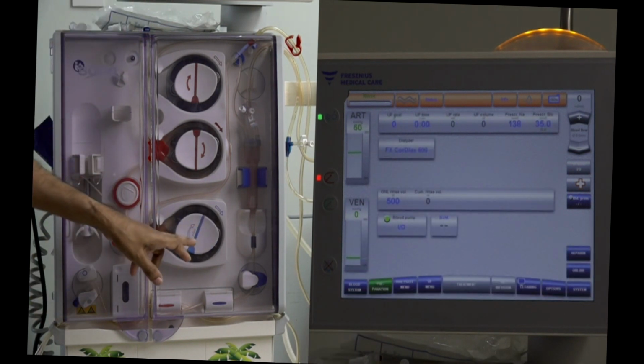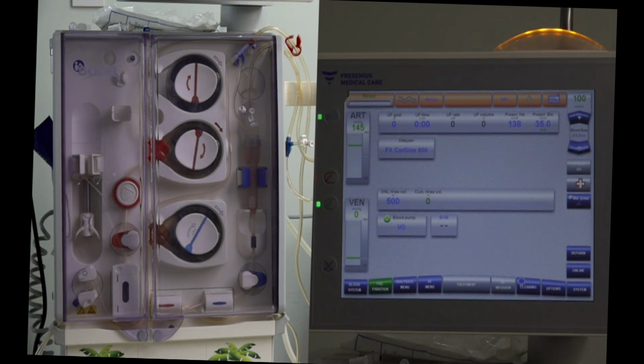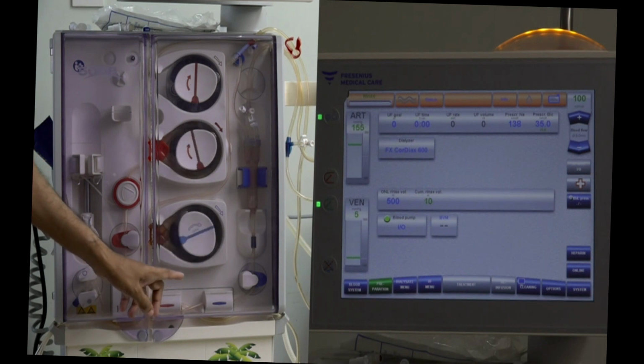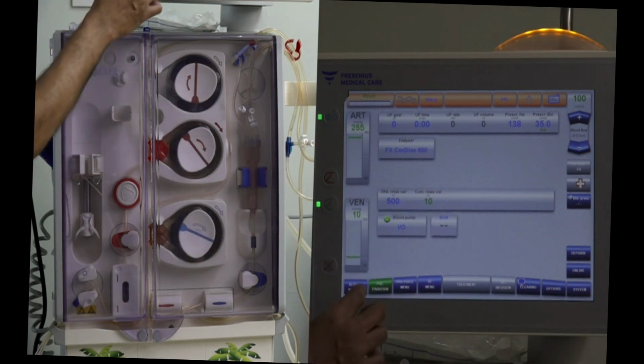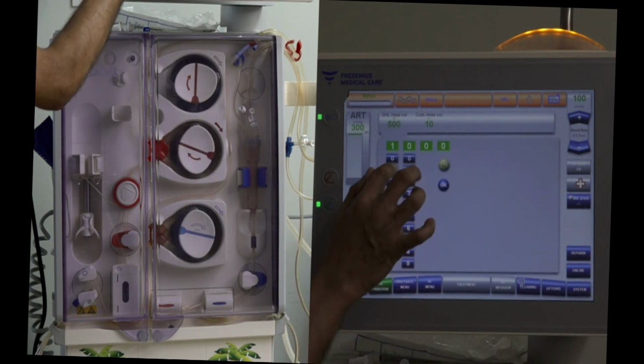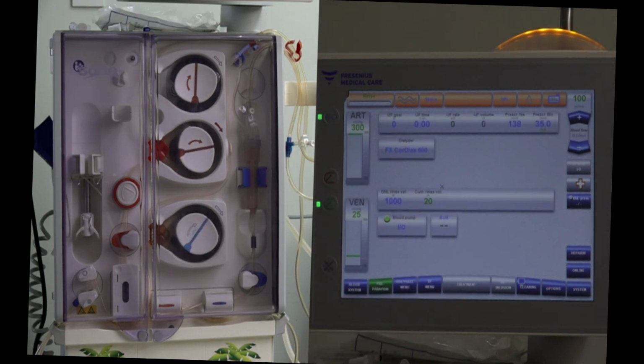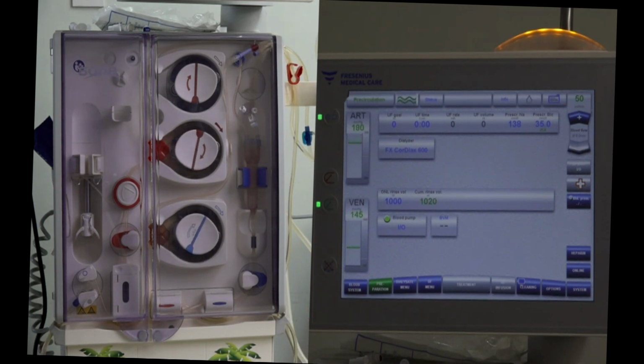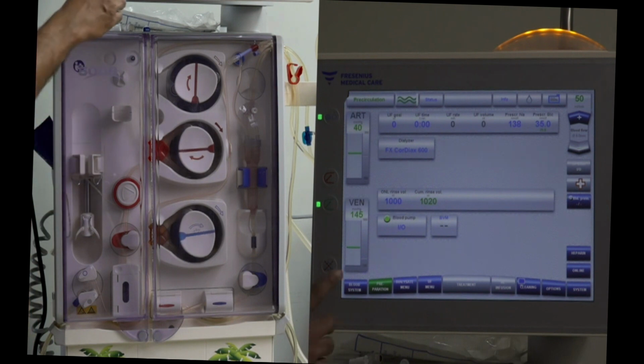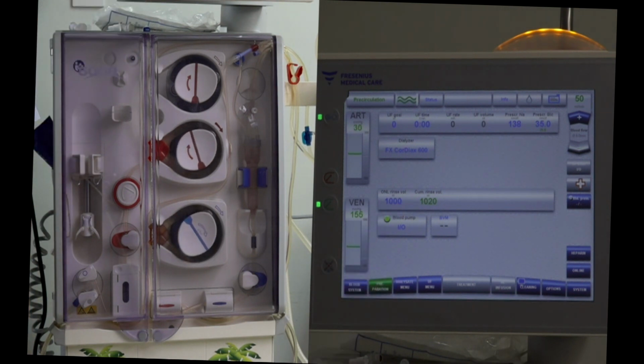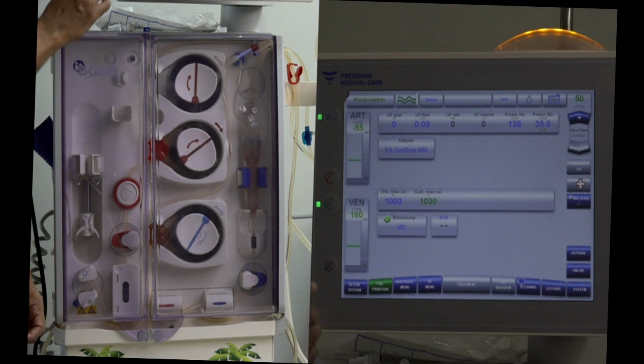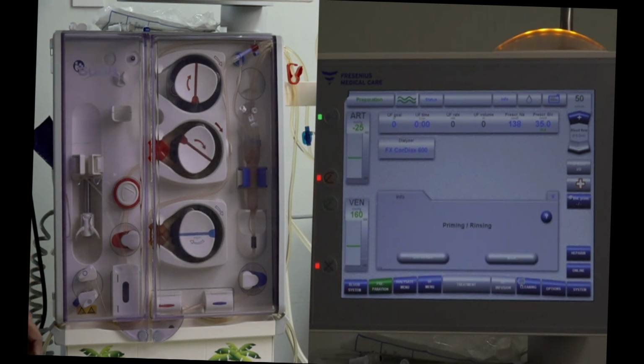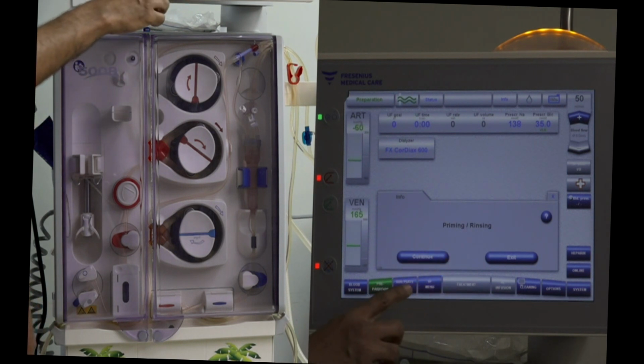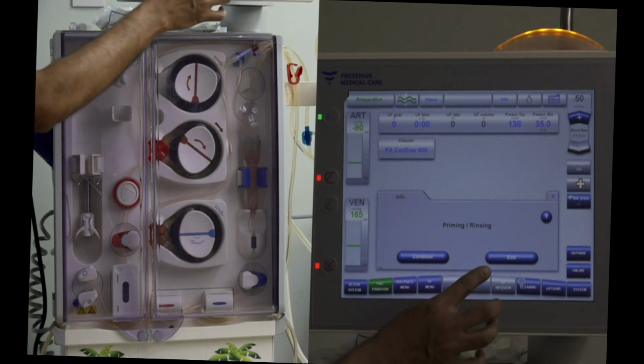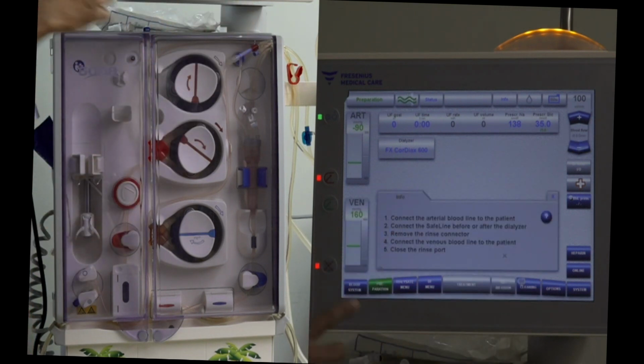And that's what has happened. Now you can see that the substitution pump is starting. It's priming at 100 ml per minute, and I'm going to keep a priming volume of 1000. As we can see here, I set the machine to prime with 1000 ml of substitution fluid, which has now been reached. So I switch the pump off, and the machine is asking me whether I want to continue priming any further or exit. I'm going to exit, and we are now ready to start the treatment.